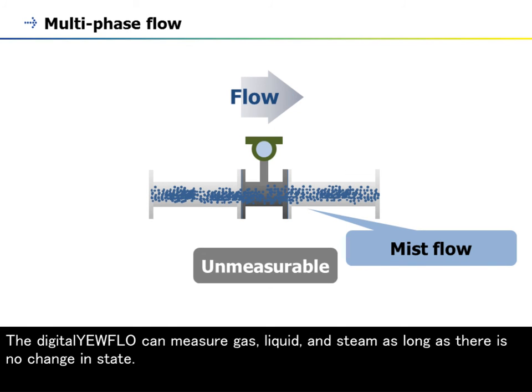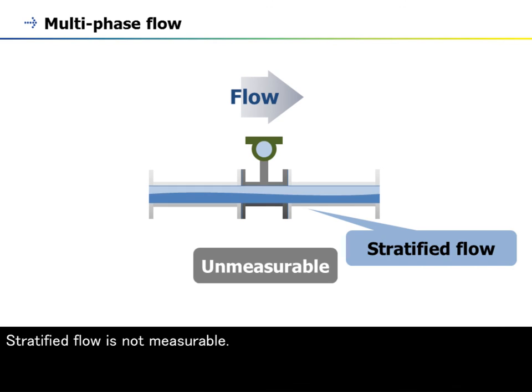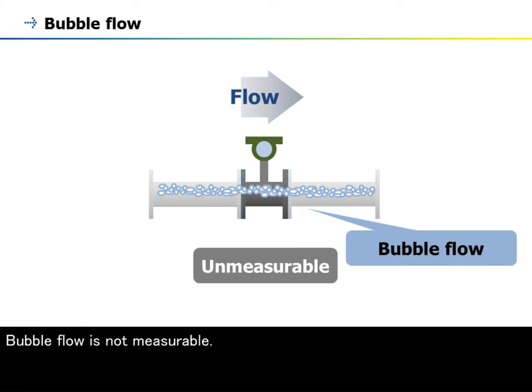The digitalYEWFLO can measure gas, liquid, and steam as long as there is no change in state. However, accurate measurement of mixed flows, such as gas and liquid, is not possible. Mist flow is not measurable. Stratified flow is not measurable. Bubble flow is not measurable.